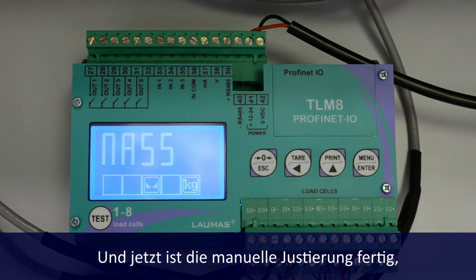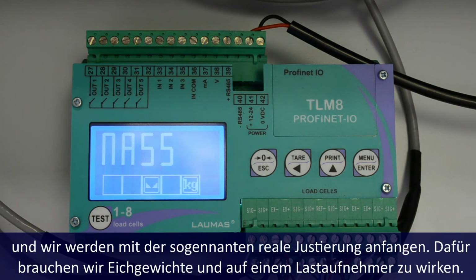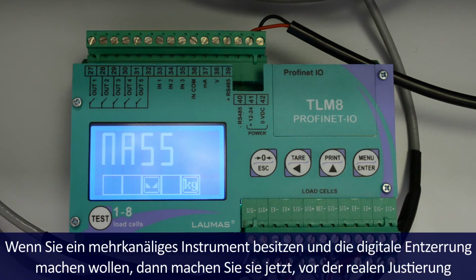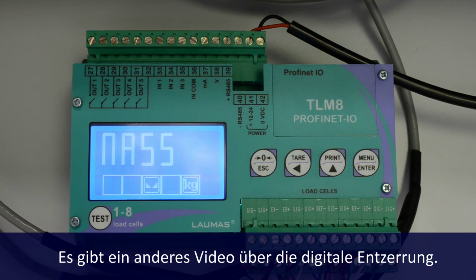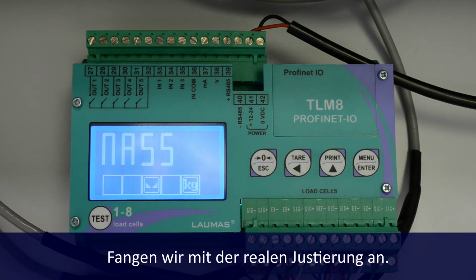Okay, now the theoretical calibration is over, and we start what we call the real calibration, that involves having sample masses and operating on the real load receptor. If you have a multi-channel device and you want to do a digital equalization, this is the moment to do it, before the real calibration. There is a dedicated video about equalization. Let's start the real calibration.